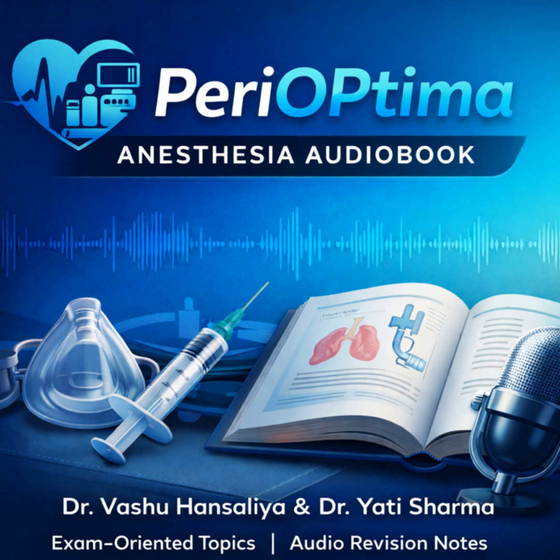And that's bad because... It can compress gas back into the vaporizing chamber, effectively giving it a double dip of vapor. It transiently increases the concentration delivered, which could potentially overdose the patient. Modern vaporizers use long spiral inlet tubes or internal baffles to prevent this retrograde flow.